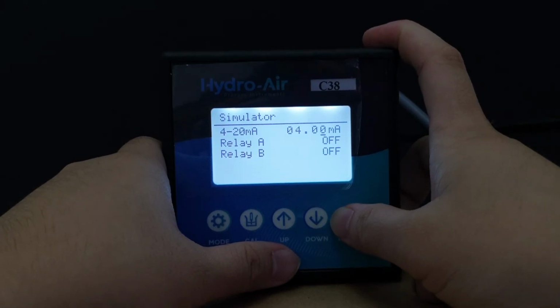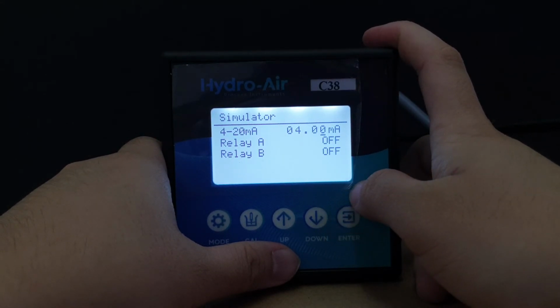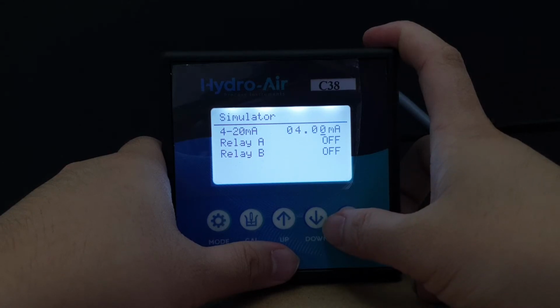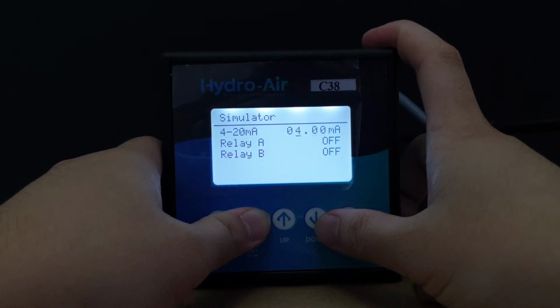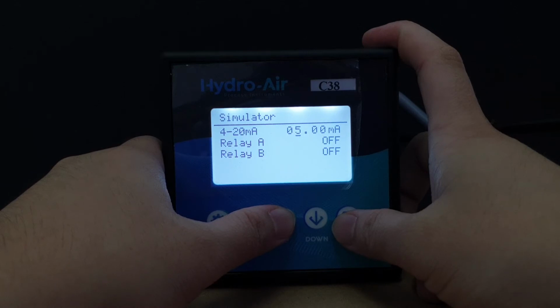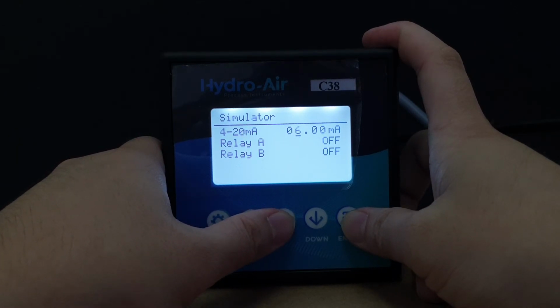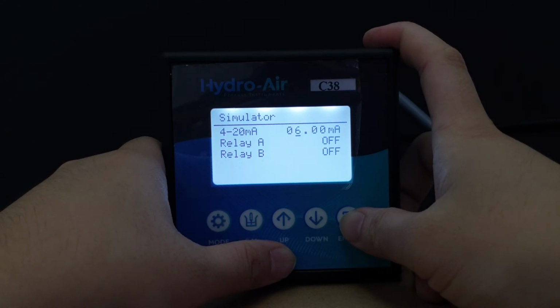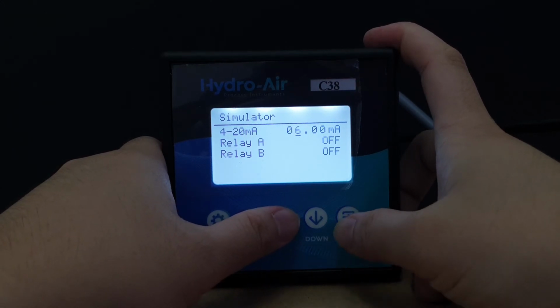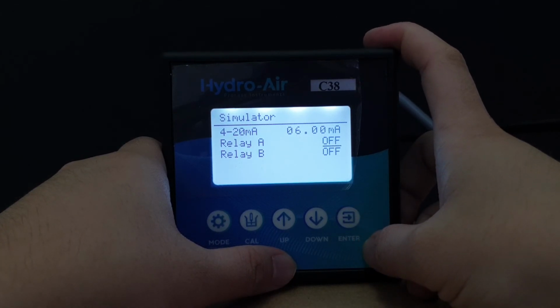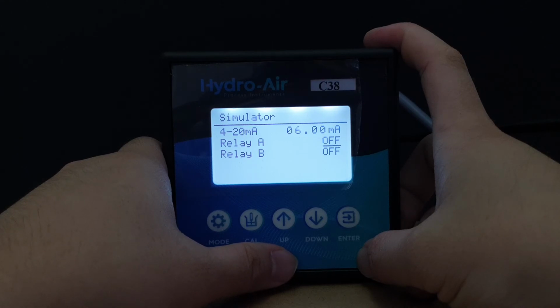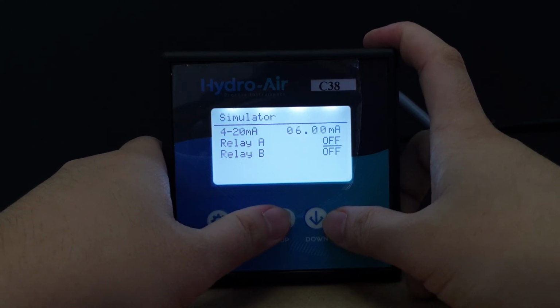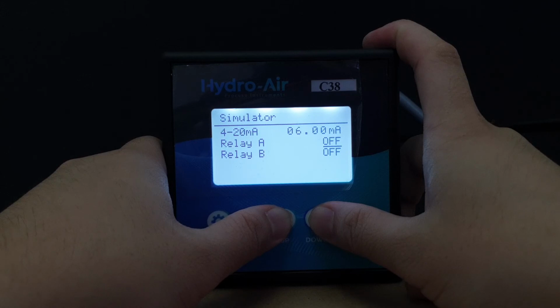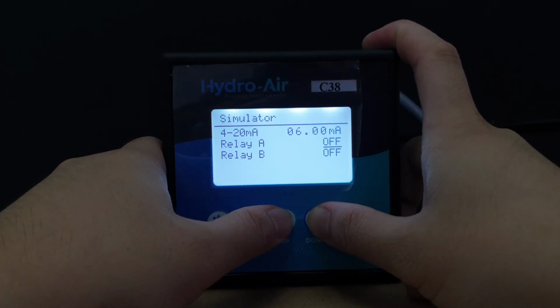The simulator is a very useful tool when it comes to testing, commissioning, or troubleshooting. Basically, the simulator allows you to simulate outputs. Say for instance, if I would like to test if the controller can inject 6 mA, all I have to do is adjust the value and press enter once. And as for now, it is injecting 6 mA through the current output. As for relay A, you can manually turn them on or off.